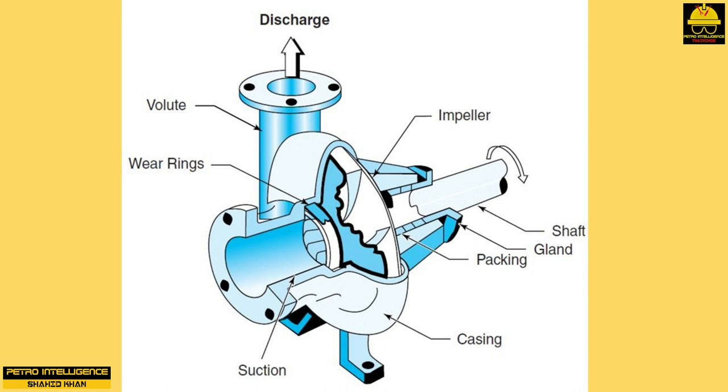The impeller is a circular device attached to the shaft. The impeller resembles a wheel of curved blades that rotates around the shaft, spinning liquid from the eye, center of the pump, to the outer casing of the pump. This liquid enters the tapered neck of the volute before exiting the pump into the discharge line. The driver is an electric motor, fixed speed or variable speed, or a steam turbine. A manufacturer's nameplate lists the important information specific to the motor: phase, horsepower, manufacturer, and type.